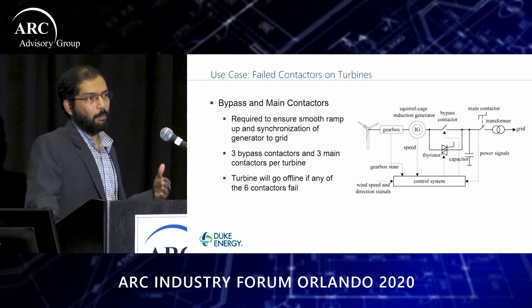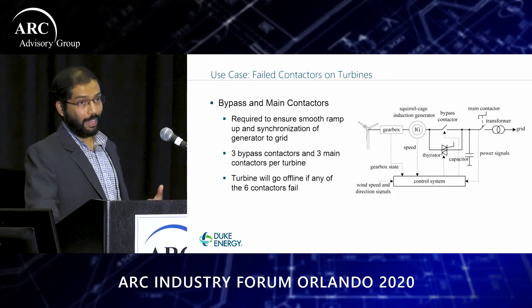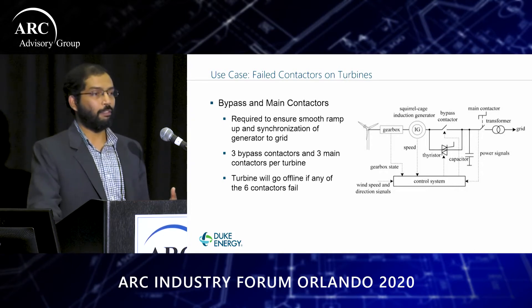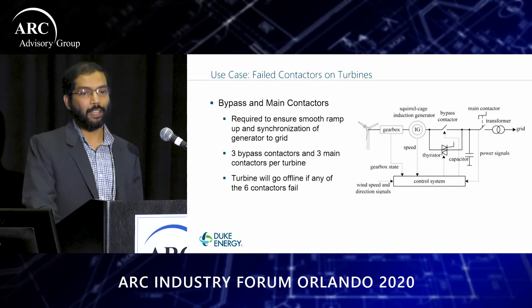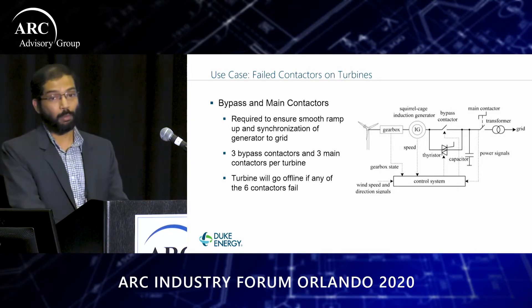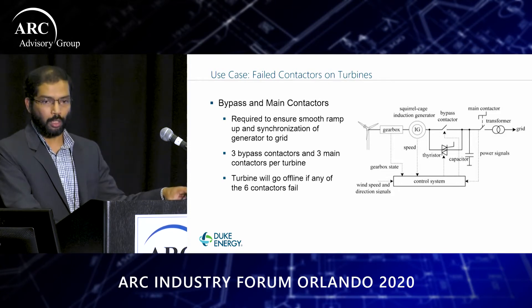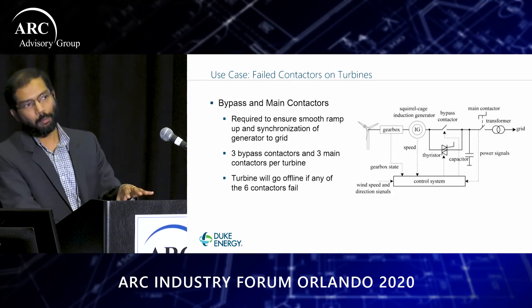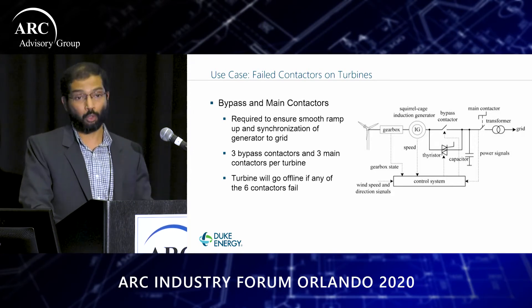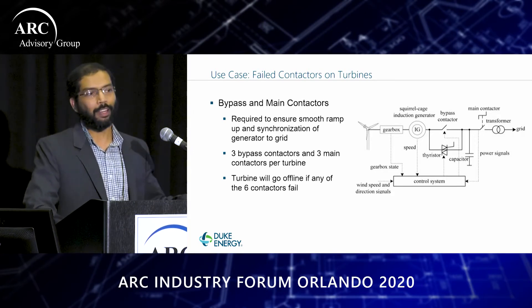The business use case is that when a contactor fails, the turbine goes offline for two to ten days. It takes a very experienced technician to go in and figure out what's wrong. It's not a simple matter of just replacing it because the fault could be upstream and then it will fail again.